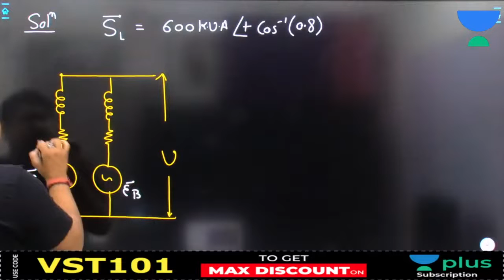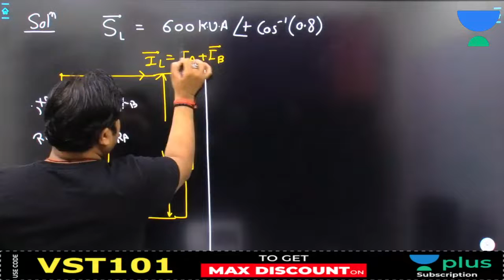Okay, sir. But when we have to use the formula for kVA shared by two transformers operating in parallel, either we have to go by the actual ohms or we have to go by the per unit impedances on a common base. That is a very important thing. Now please observe here. This load is given to you. This is the punch point of this question. Please observe. The current IL is equal to IA plus IB, phasor sum. This is your IA and this is your IB.